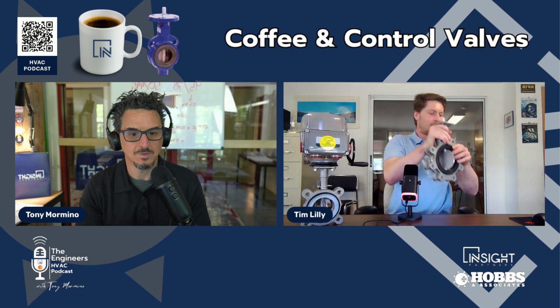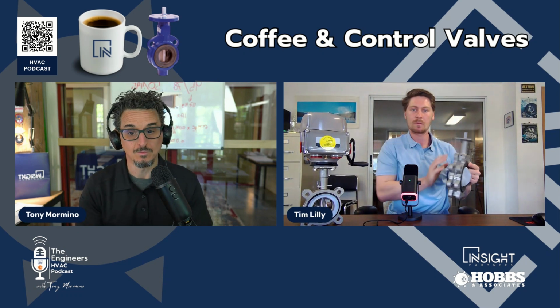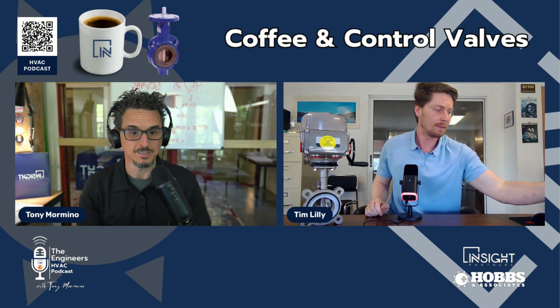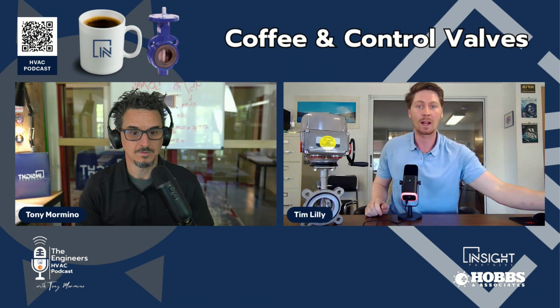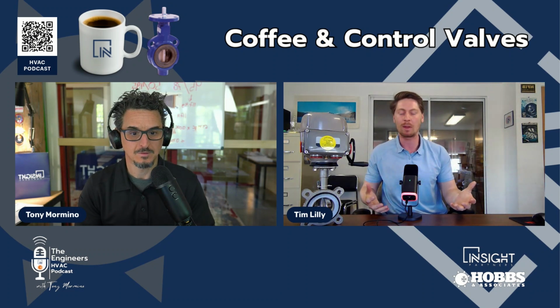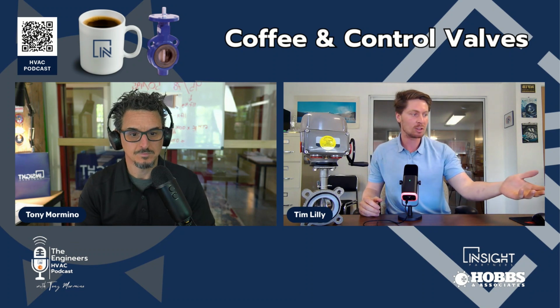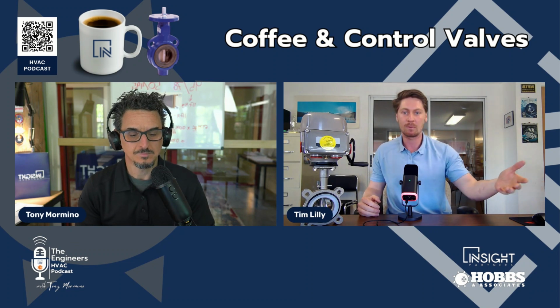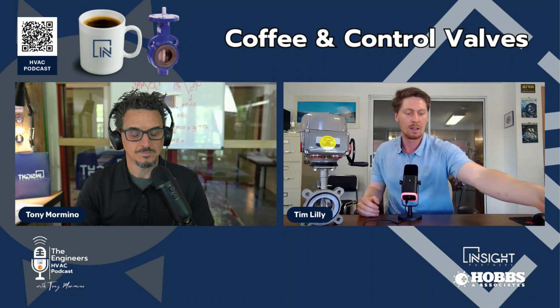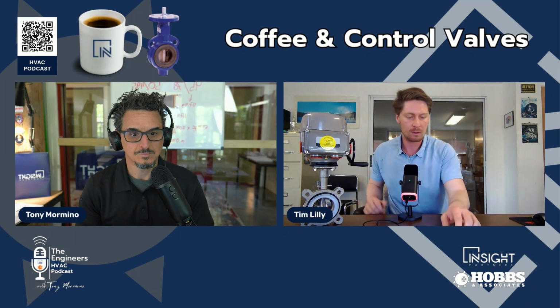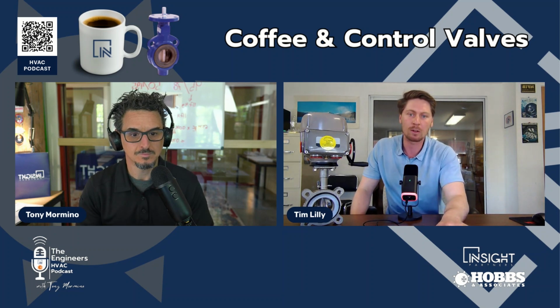Gotcha. And unless you've got some very expensive water flow meters, flow monitors in there, which are expensive. Right. And then you have to figure out a way to program it. And it's a hassle. But most HVAC folks have to put it in because a 6-inch butterfly valve weighs 22 pounds, whereas a 6-inch characterized ball valve weighs 93.